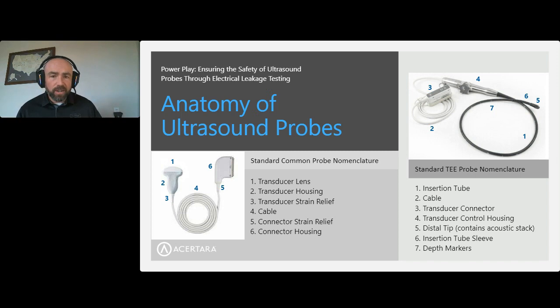So, moving quickly here, the cable is going to be similar to what you see on GE probes. The connector and the strain relief are going to be similar to what you see on GE probes. I've described the control housing a bit before. You can see the articulation knobs there. Those can get loose over time. So when you're doing an inspection, if you rotate that device and you have to rotate it some portion of a full rotation before you start seeing the actual tip rotate, that's a good indication that the probe needs service, because you want a nice crisp response when you move those articulation knobs. And as I said, it's two 180-degree planes that are perpendicular to one another. So the probe can move in this direction, and then it can also move in this direction.